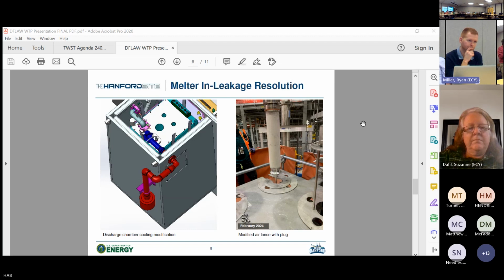So this got put in the late January timeframe. Immediately prior to putting in the air lances, it was completely effective. That part of the chamber now is at the temperatures that it should be. It's operating exactly as intended. And when we put these air lances in, the plugs, we put those in early February. We were able to get immediately to -5 inches without challenging the film cooler. They stress tested that. They tried to put it through perturbations to confirm that we weren't going to challenge the film cooler at our highest flows and highest negative vacuums in the plenum. And it passed all of that.